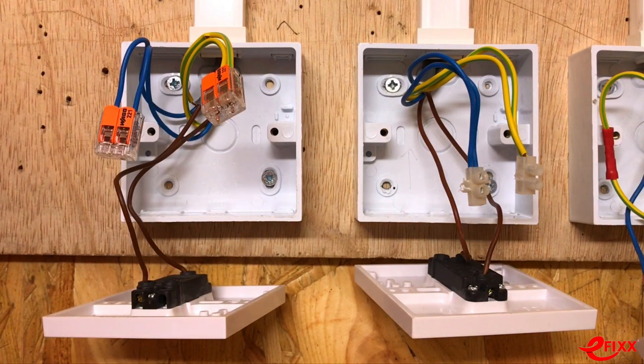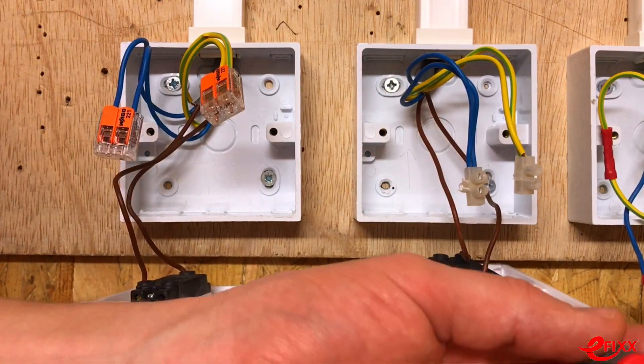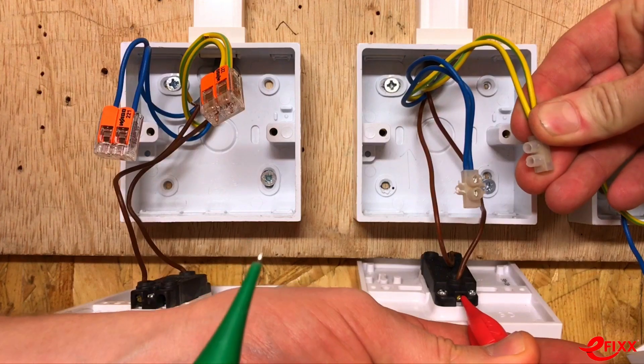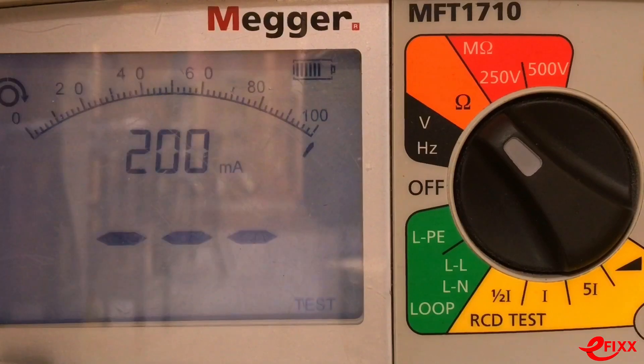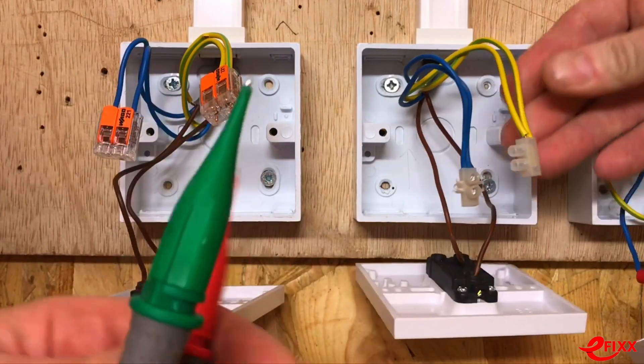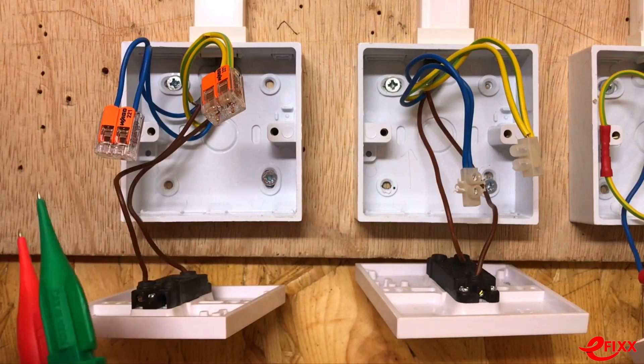We're at the crucial stage where the electrician must prove the circuit protective conductor reaches every point in circuit, including down to the switch. Starting with the 5-amp traditional connector block — one probe on the common terminal, the other probing into the screw of the connector block. The meter reads 0.12 ohms, and it was very easy to get onto that connector.